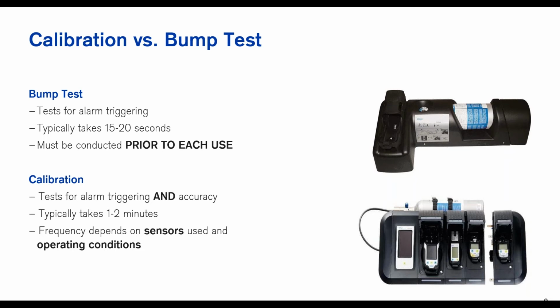But the frequency depends on, again, not only the sensors that you're using, but also your operating conditions. A lot of meters, I'm not going to say all, but a lot of meters will tell you to calibrate at least twice a year, maybe every 6 months. And so that's typically at a bare minimum. But if I'm using it all the time, so I've got a history in the fire department. We're going into house fires literally every shift.